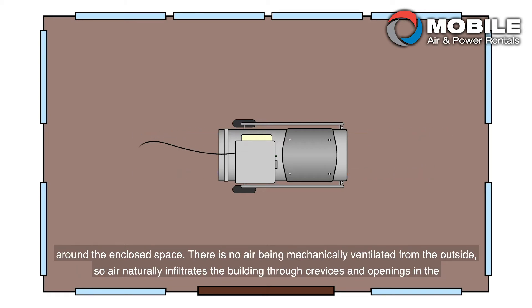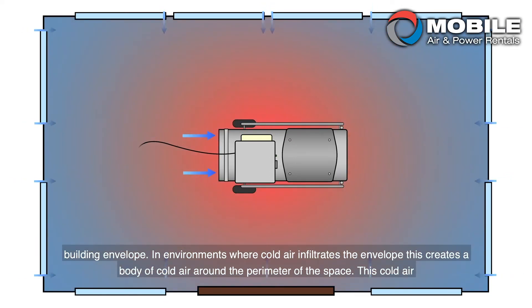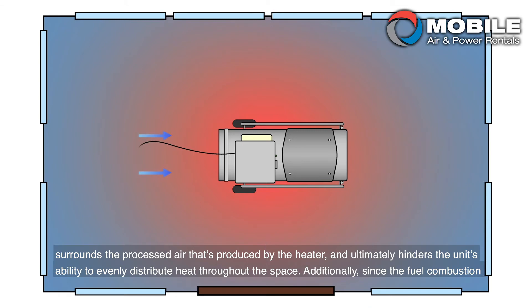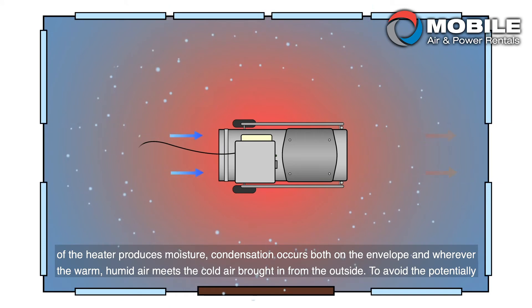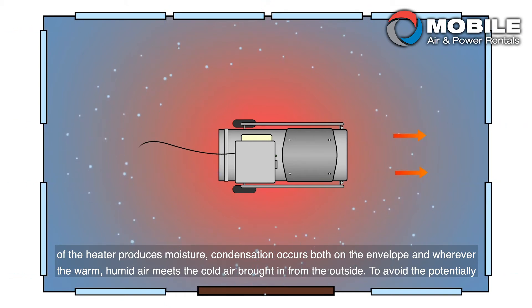Here a direct-fired heater is staged in the center of a building, where it recirculates heated air around the enclosed space. There is no air being mechanically ventilated from the outside, so air naturally infiltrates the building through crevices and openings in the building envelope. In environments where cold air infiltrates the envelope, this creates a body of cold air around the perimeter of the space, which surrounds the processed air produced by the heater and ultimately hinders the unit's ability to evenly distribute heat. Additionally, since the fuel combustion of the heater produces moisture, condensation occurs on both the envelope and wherever the warm, humid air meets cold air brought in from the outside.